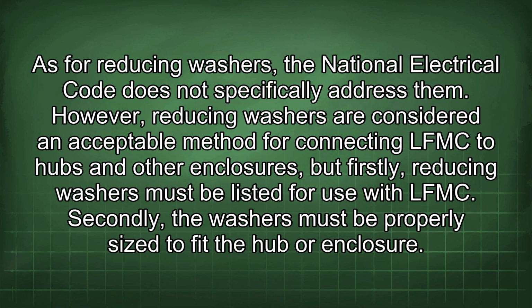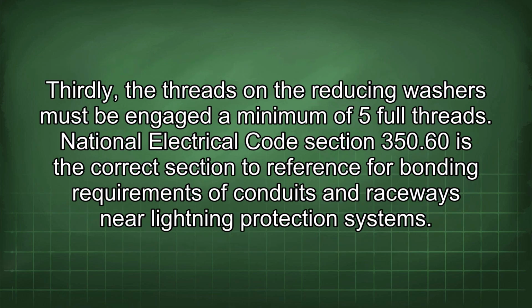As for reducing washers, the National Electrical Code does not specifically address them. However, reducing washers are considered an acceptable method for connecting LFMC to hubs and other enclosures, but firstly, reducing washers must be listed for use with LFMC. Secondly, the washers must be properly sized to fit the hub or enclosure. Thirdly, the threads on the reducing washers must be engaged a minimum of 5 full threads.